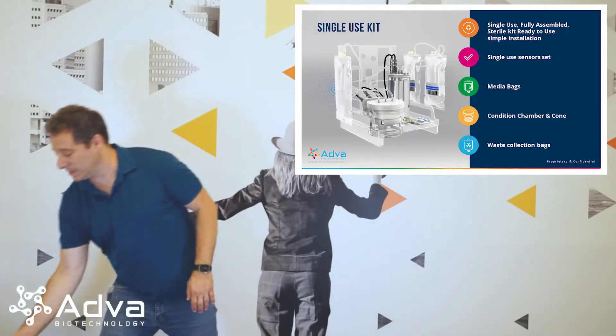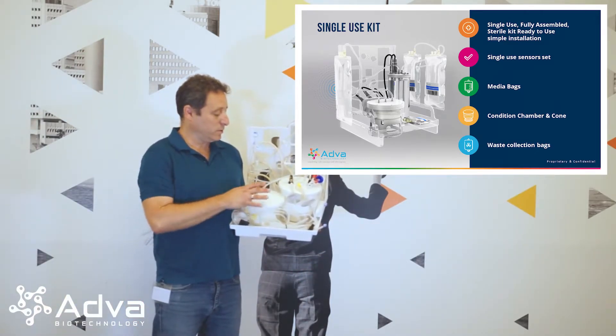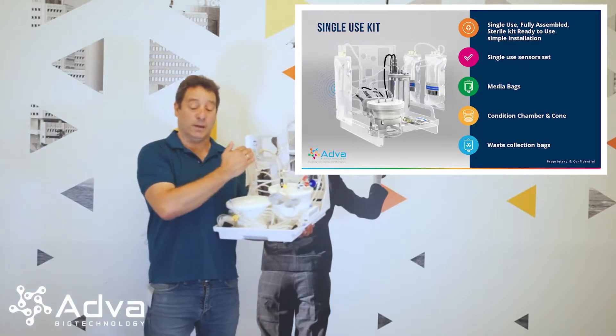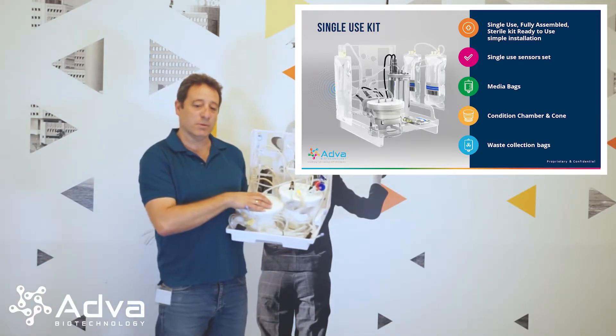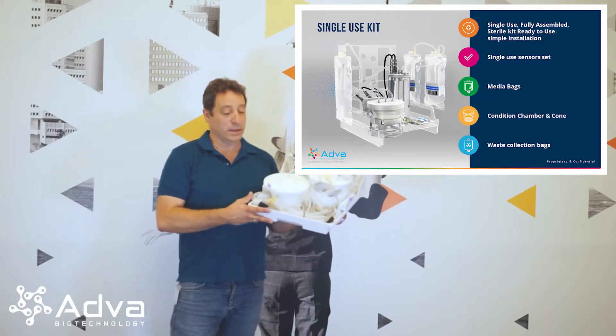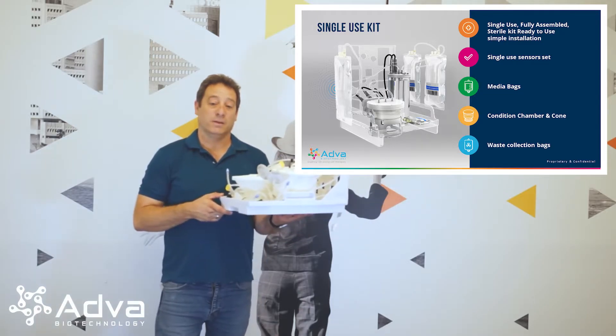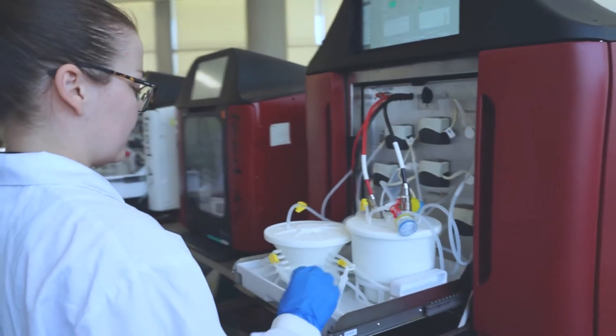The other part of the system is basically a single-use kit with four different elements. The first is the reservoir, or what we call the conditioning chamber, whose purpose is to take media from the refrigerator, put it into the tank, and condition it to the temperature, pH, dissolved oxygen, glucose, and lactate levels that we want, then feed the cone. The second part is the cone, which is the culture chamber. The third part is all the tubing, sensors, etc. The kit comes pre-assembled on a tray that is very easily settled inside the drawer — every tube is in front of its correct pump, so the assembly is very simple and straightforward.